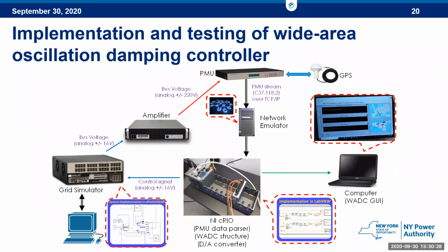This is an example project that is ongoing, looking at the design of a wide area oscillation damping controller. It had several phases, done in collaboration with EPRI and the University of Tennessee, with NYPA participating as well as Terna from Italy. The idea is straightforward: design a controller that looks at multiple locations of the grid, taking PMU angle measurements from multiple locations to detect oscillations happening in the grid.